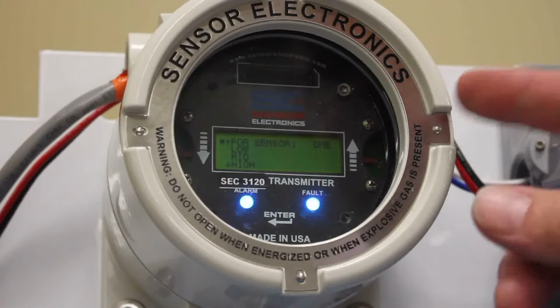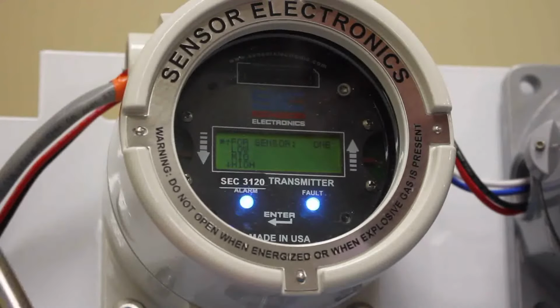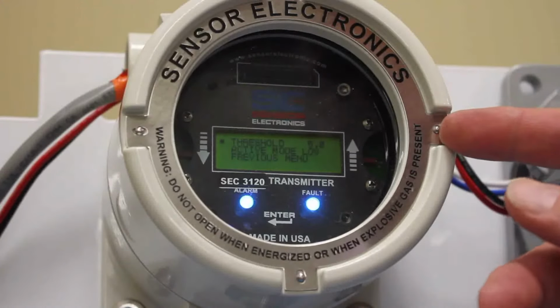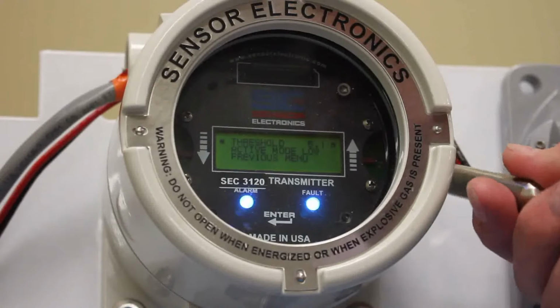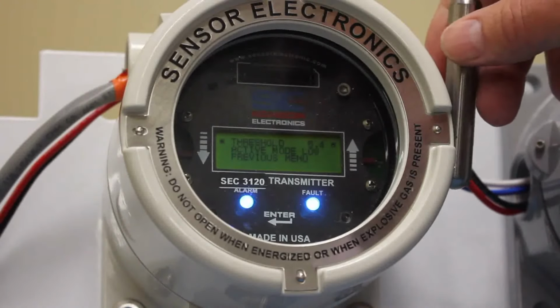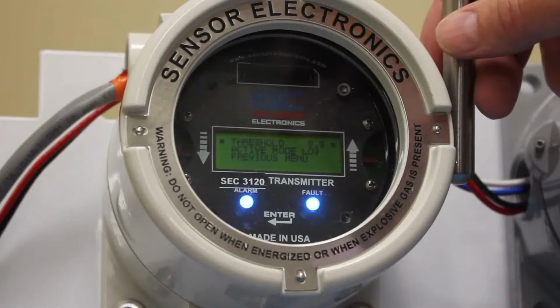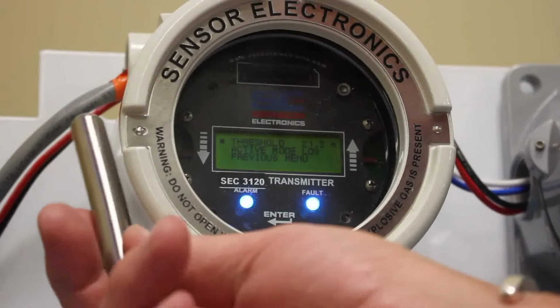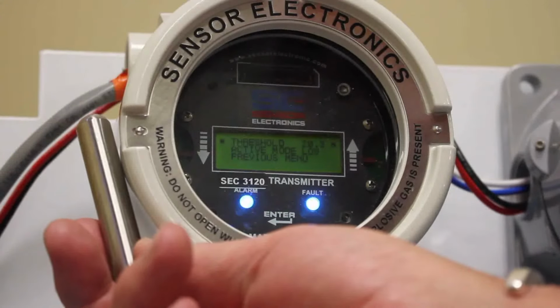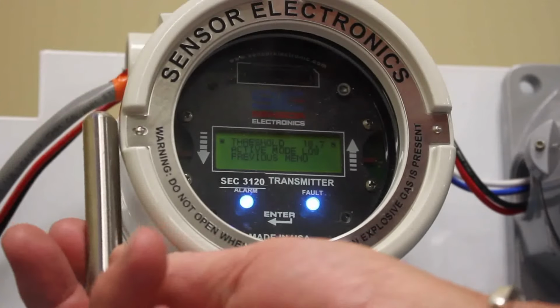and since the oxygen sensor's on ID number 1, we'll select 1, and we'll go into Low Alarm, and you can see the default is set for 5. Typically what we set the low alarm for oxygen sensors is 16.5. So we just select Enter and then use the up arrow to get our alarm set point correctly set. Oops, I went too far. So then we want to get it again to 16.5% by volume for our low alarm.